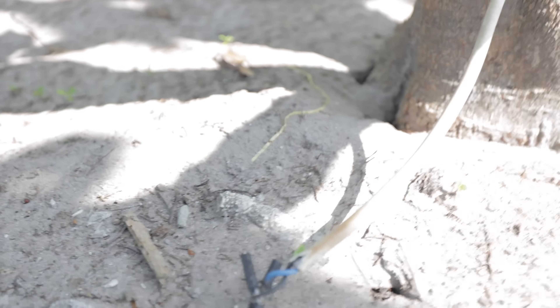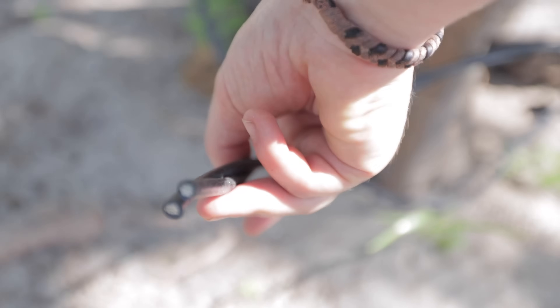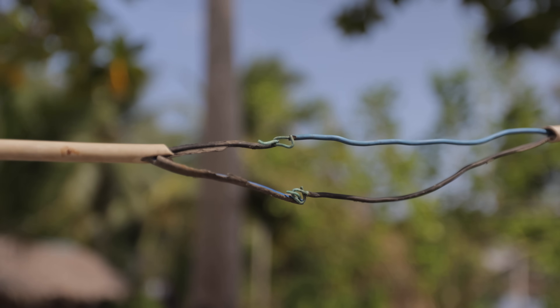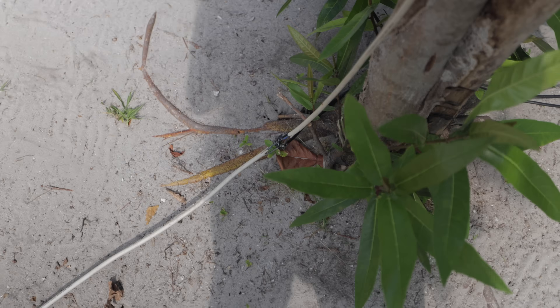There are a lot of loose ends of wires here — I'm not quite sure if they're live or not. That one is just a loose piece of wire not doing anything. This one comes out of the ground and it's quite thick — aluminium conductors — but not doing anything either. Here a cable comes under the ground, wires are twisted together and split off. That's how they do cable joints here — they basically hooked the copper wire over each end and hooked it together, and it's quite corroded, so it's clearly got wet.